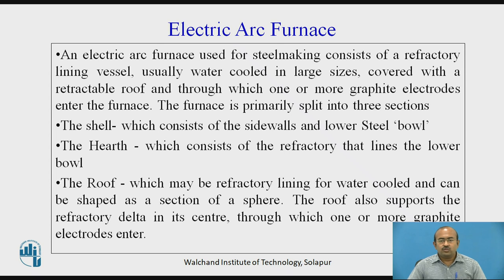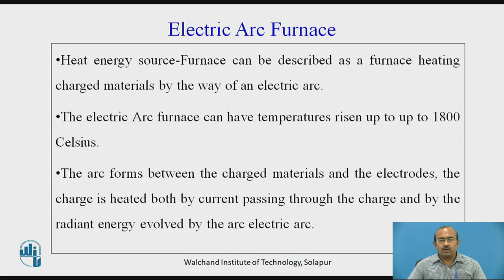The roof also supports the refractory delta at its center through which one or more graphite electrodes enter. The heat energy source for this furnace is an electric arc, which can raise temperature up to 1800 degrees Celsius. The arc forms between the charged material and the electrodes. The charge is heated both by current passing through the charge and by the radiant energy evolved by the electric arc.